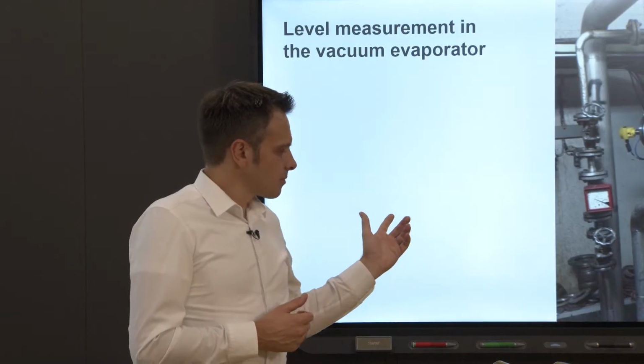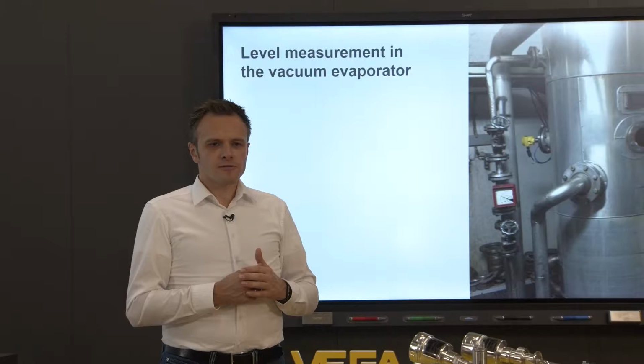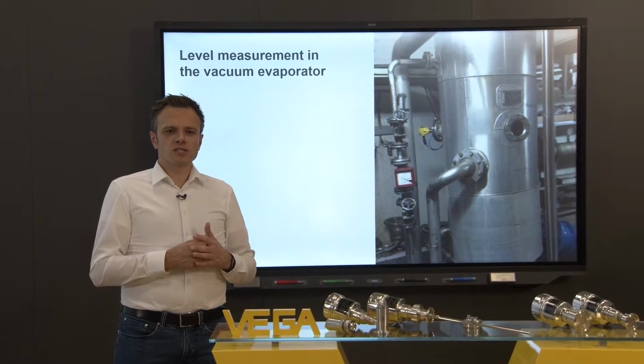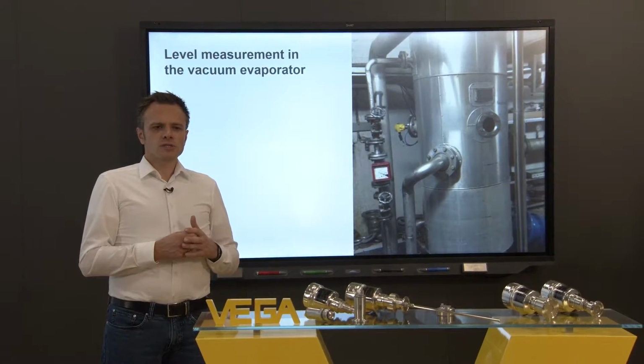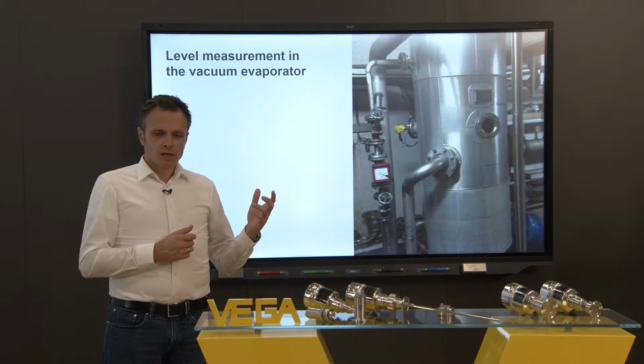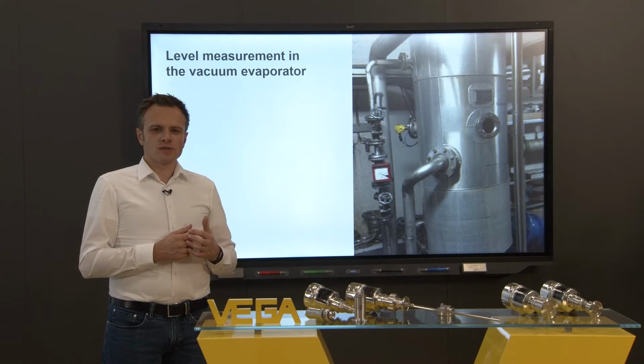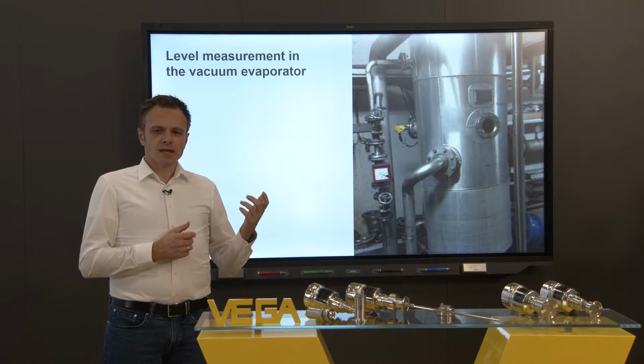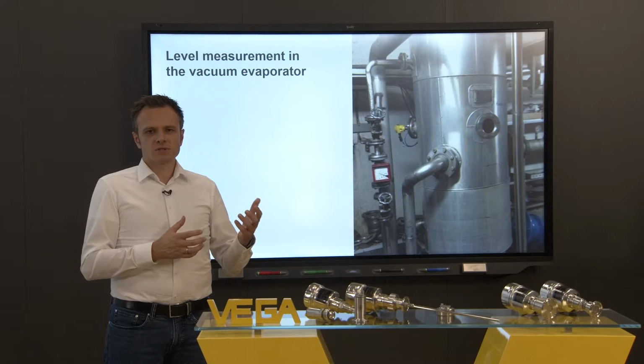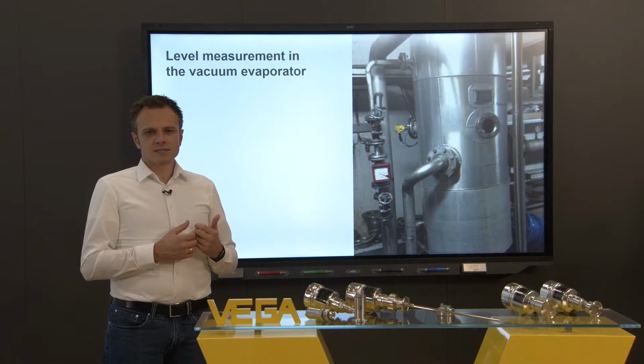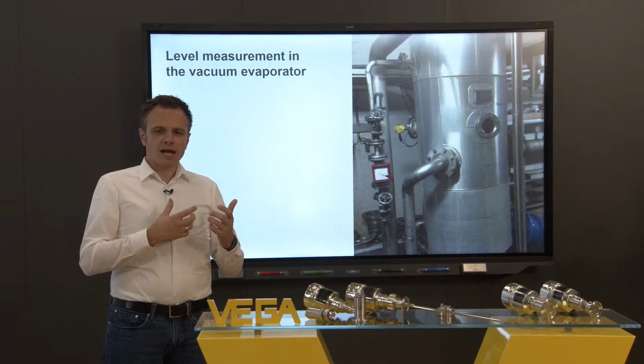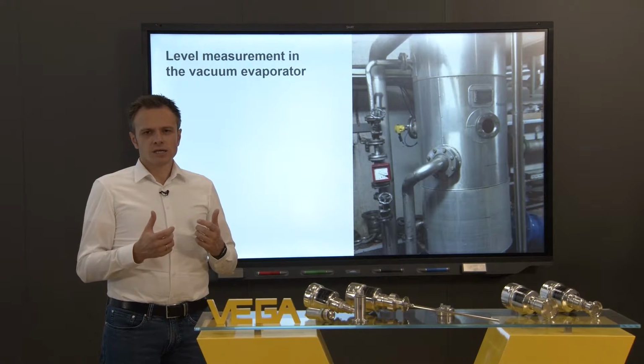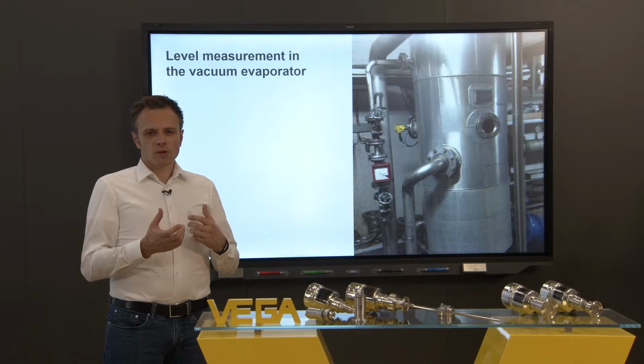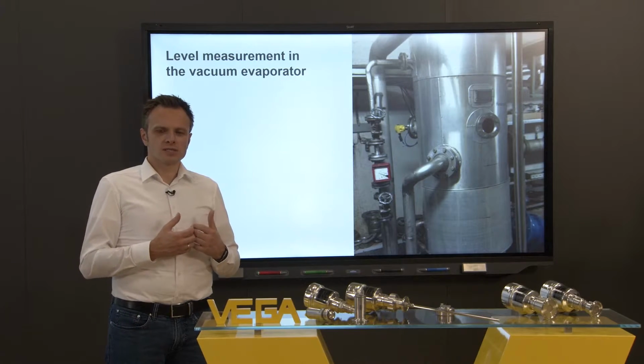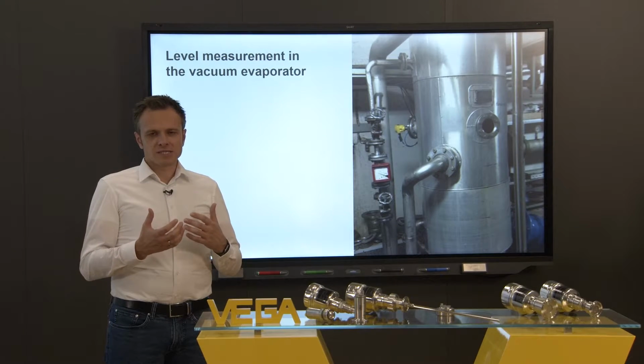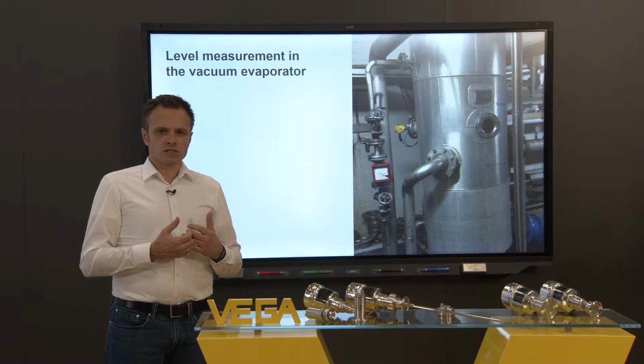Same application, but different measurement. We have the electronic differential pressure. In that solution, we measure the pressure and we measure out the level of that. Typically, we use classic differential pressure with a capillary line, an oil-filled system. Oil filling with high temperature and low pressure often gives the problem of a drift. You have to recalibrate the sensor often, and at a specific time, you have to replace it.